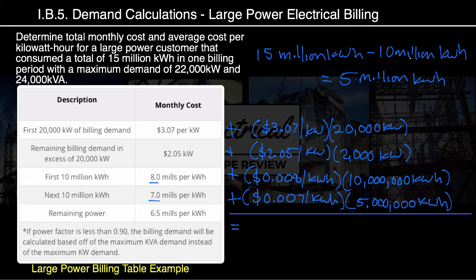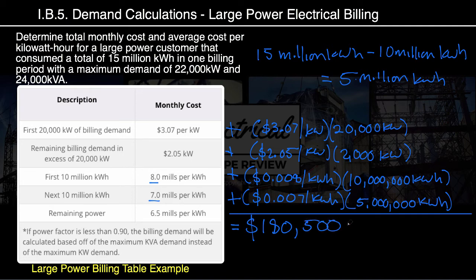Now it's time to find our total power cost. From left to right, top to bottom in the calculator: $3.07 times 20,000 plus $2.05 times 2,000 plus $0.008 times 10,000,000 plus $0.007 times 5,000,000. I hit enter on my calculator and get a total charge of $180,500. That's our total monthly bill.